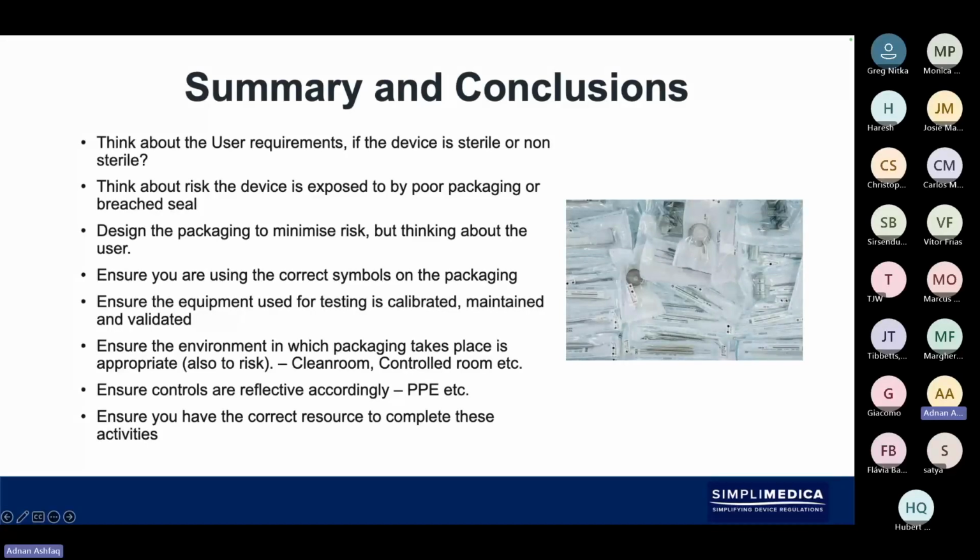Assuming the regulatory authorities may look at the technical documentation, then it's still a requirement. The safe answer is that you should be performing transport validation regardless of classification. But what you need to look at most importantly is the risk.